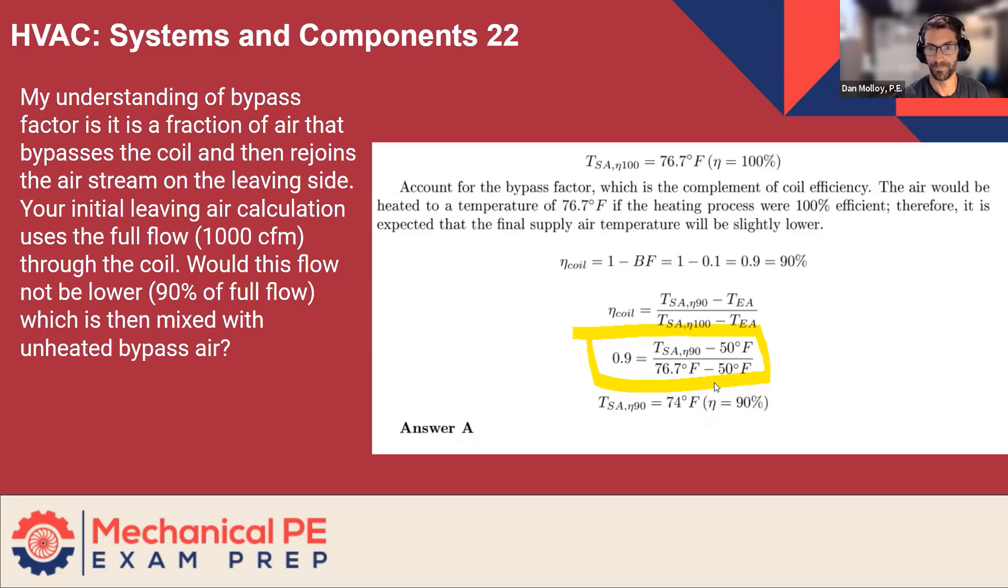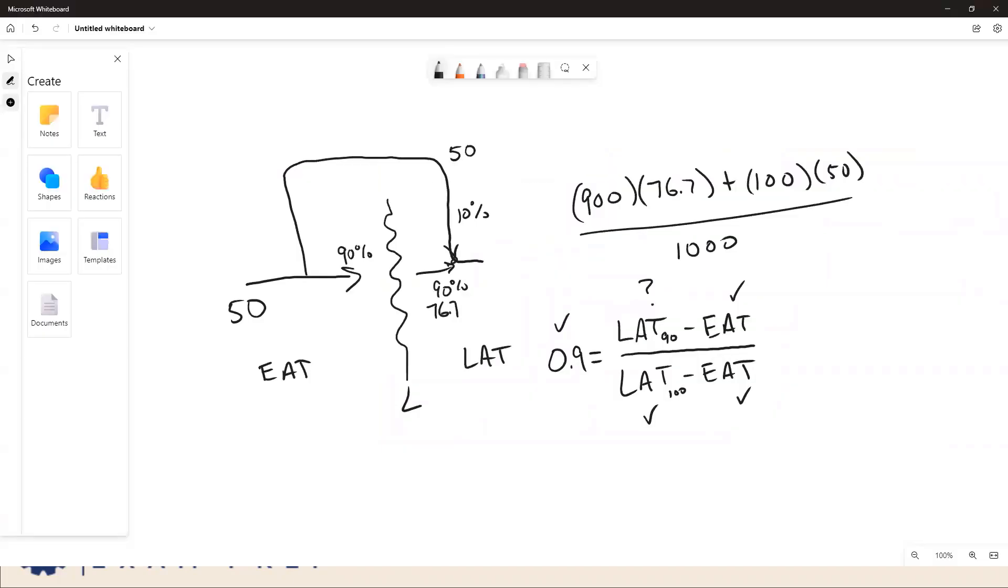Hey, Dan. Yeah, go ahead. I'm sorry, I was trying to do the unmute and I was unsuccessful. This is Bill. Hey, Bill. And so when I was looking at that, okay, if you assume 10% goes around, then your T supply air leaving the coil would be based on 900 CFM and not a thousand. Yeah, I agree.